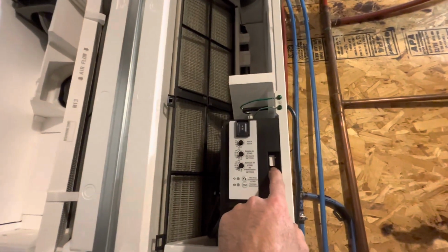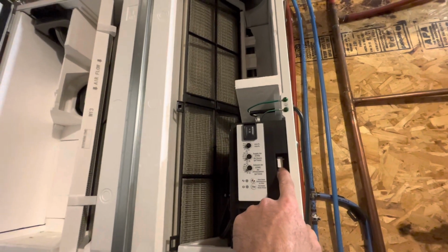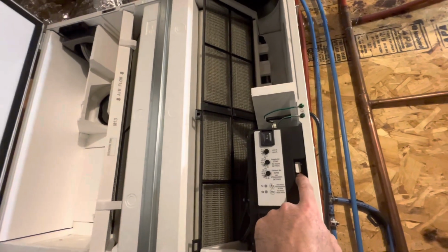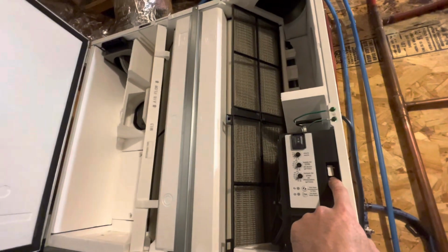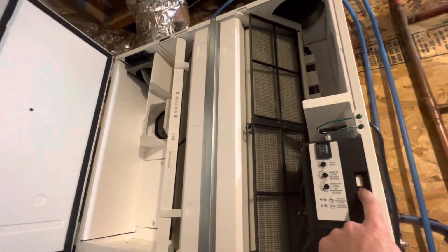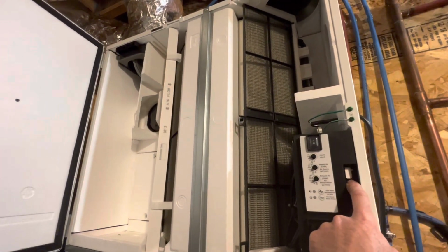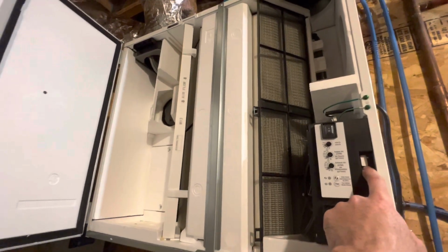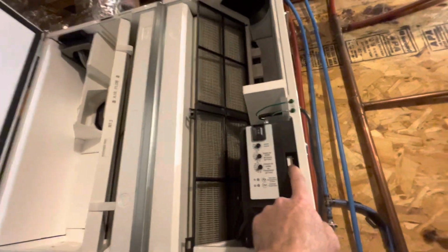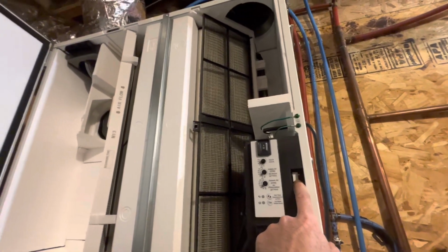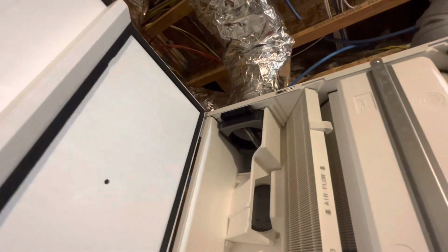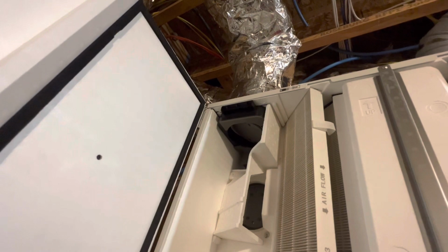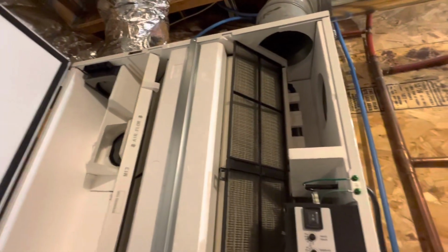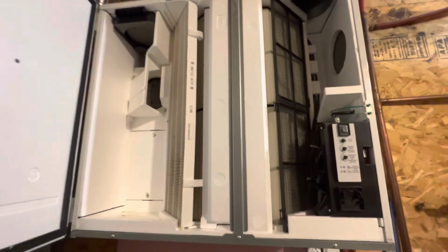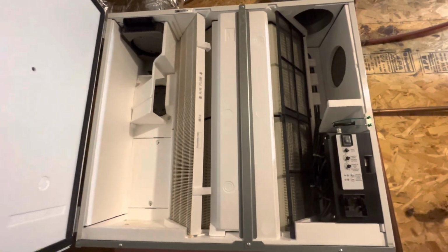Here's the door switch button that essentially stops everything, shuts the motors off, and locks the dampers in position. Since I opened the door and the controller upstairs has it in the off position, if I push this button, those dampers will drive closed. You can see they're driving closed. And now all the dampers are closed and the unit is essentially sealed up from the outside air.